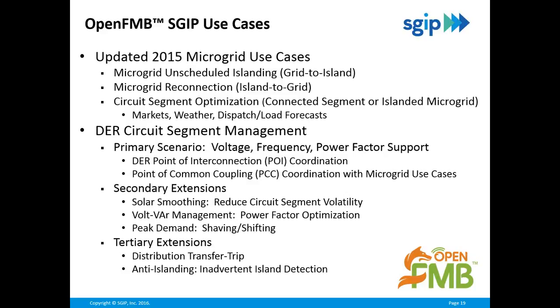Some of the key parameters that are given essentially as boundary conditions and schedules at the point of interconnection are voltage, frequency, and power factor. As long as you stay within those boundaries of the primary scenario, then you can start to consider some additional performance-based use cases. We call these secondary extensions.